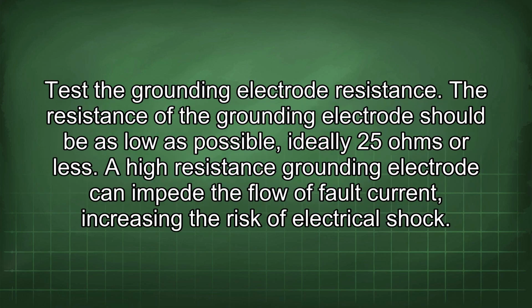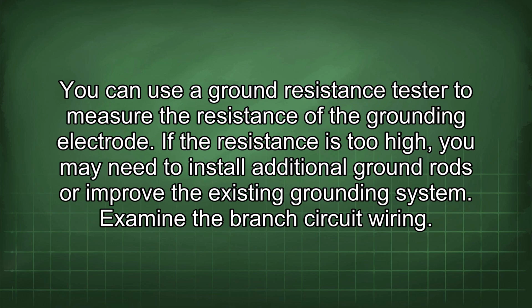Test the grounding electrode resistance. The resistance of the grounding electrode should be as low as possible, ideally 25 ohms or less. A high resistance grounding electrode can impede the flow of fault current, increasing the risk of electrical shock. You can use a ground resistance tester to measure the resistance of the grounding electrode. If the resistance is too high, you may need to install additional ground rods or improve the existing grounding system.